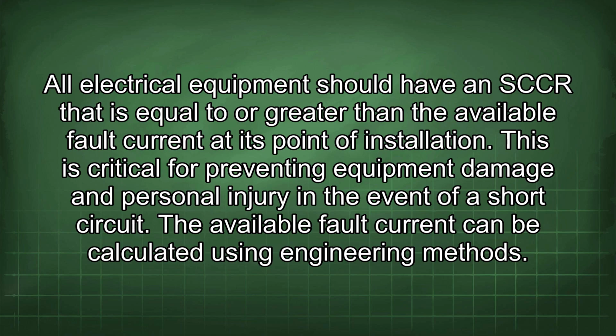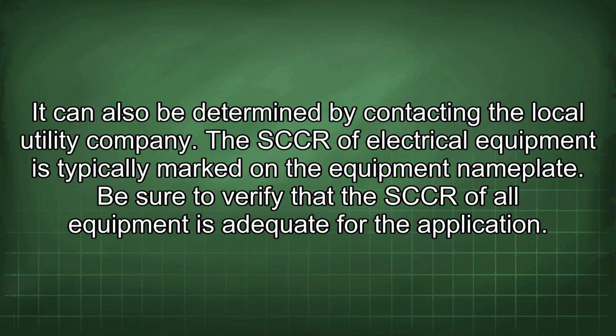The available fault current can be calculated using engineering methods. It can also be determined by contacting the local utility company. The SCCR of electrical equipment is typically marked on the equipment nameplate. Be sure to verify that the SCCR of all equipment is adequate for the application.